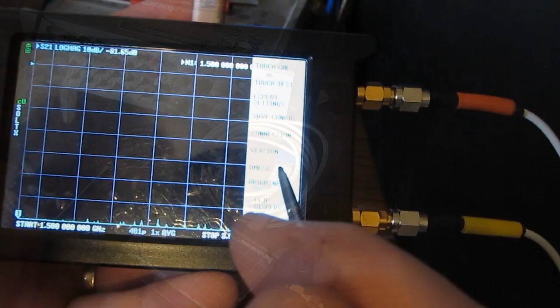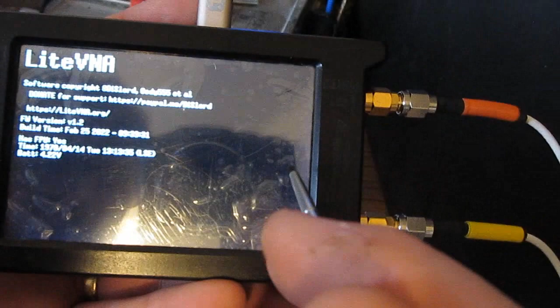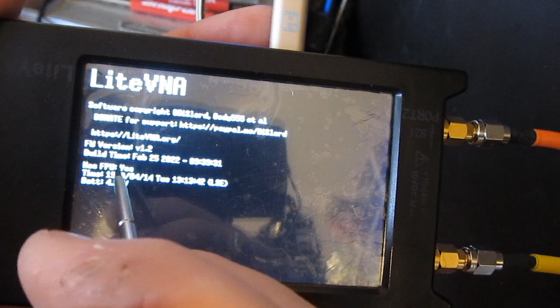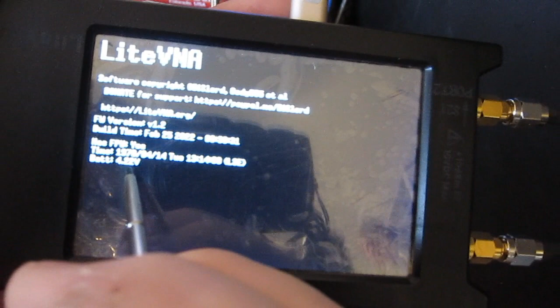you can see the software now reports that it's Protocol 1, Firmware 2.2. If we go ahead and select the version, you can see it reports it's the LiteVNA Firmware version 1.2. Build time February 25th of 2022. You can see it also reports that it has the floating point unit. This one is showing a battery voltage of 4.22 volts.